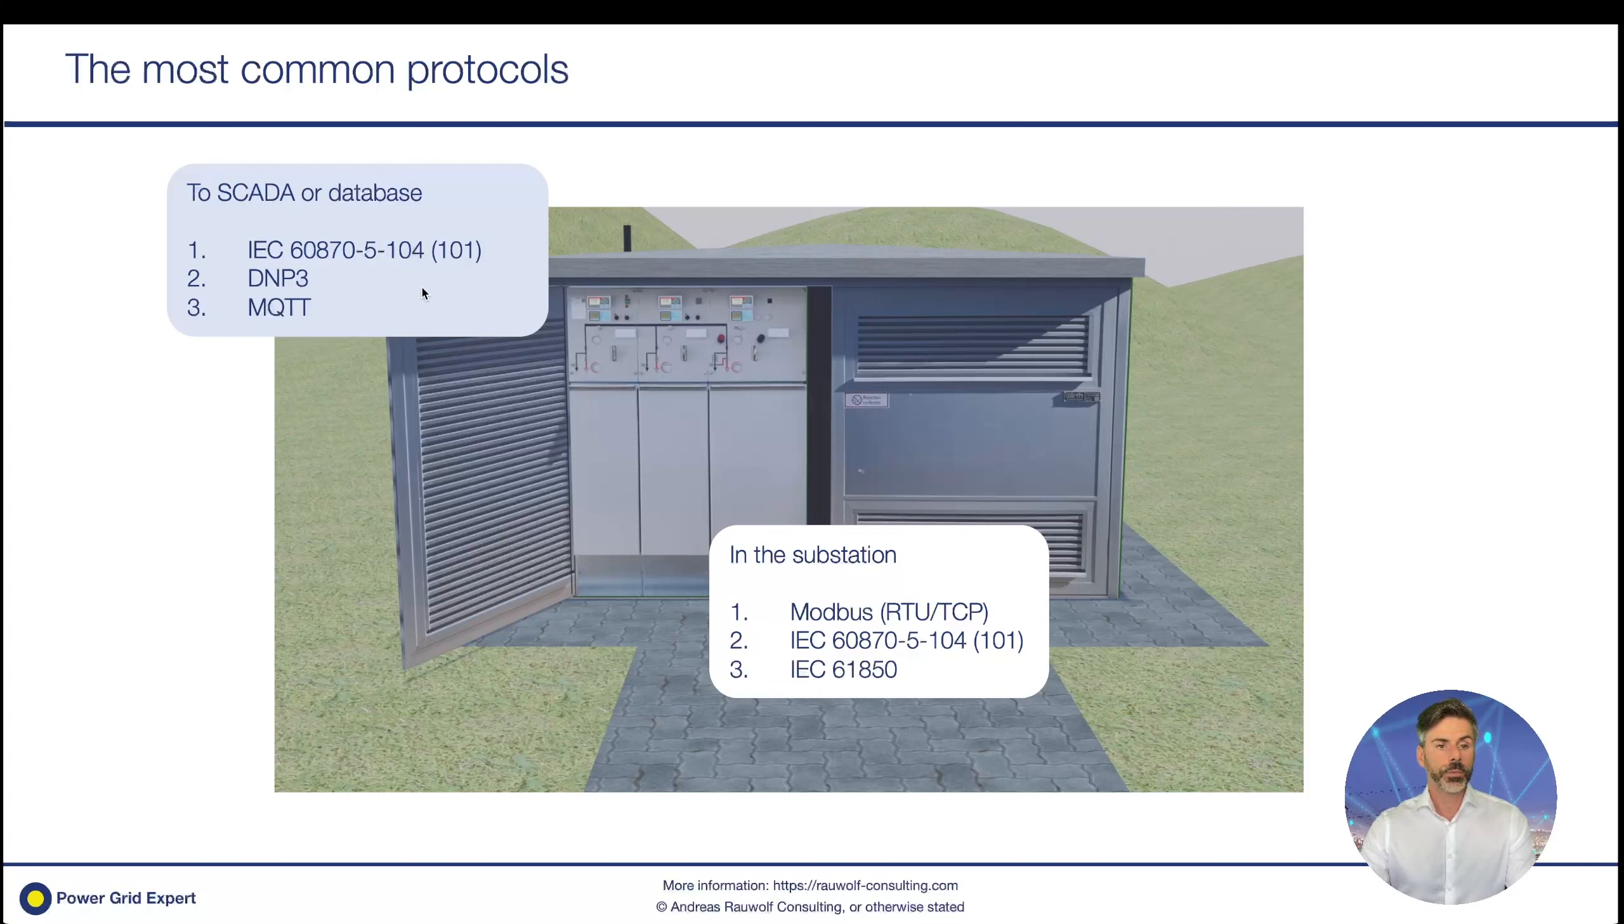To communicate to the SCADA system, we again have the IEC 104 and 101, and this was the original idea of using this protocol to communicate between the RTU and the SCADA system. The competitor protocol, so to say, DNP3, is pretty much similar to the 104 and 101. In my personal opinion, the differences are marginal, though other people might have other opinions here. A relatively new protocol in the application for utilities is MQTT, we will also have a look at that.